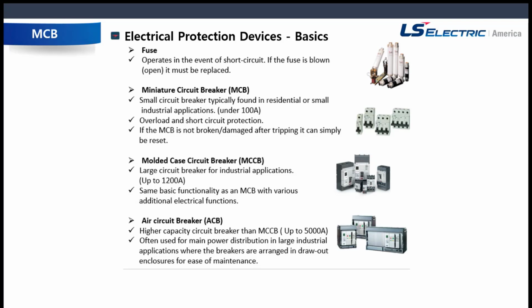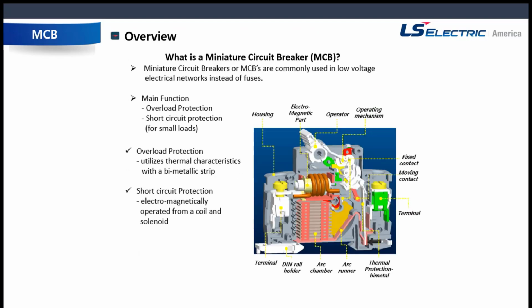Molded case circuit breakers work with much higher amperage. As you can see, they go up to 1200 amps and are used for mostly industrial applications. They provide the same basic functionality as an MCB, but because they're larger, they're going to be able to do a bit more, and they've got more electrical functions. The air circuit breaker is a higher capacity circuit breaker than the MCCB, and they go all the way up to 5,000 amp. Those are used for main power distribution in large industrial applications, where breakers are arranged in draw-out enclosures for ease of maintenance. We actually work with quite a bit of ACBs, and if you call us up and talk to John Lee, you know that we work with ACBs as well. We've got quite a lot of products in that range.